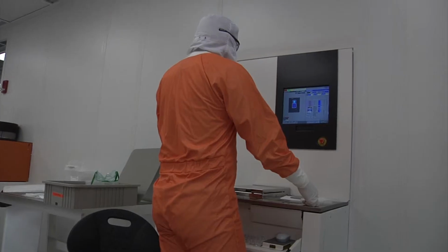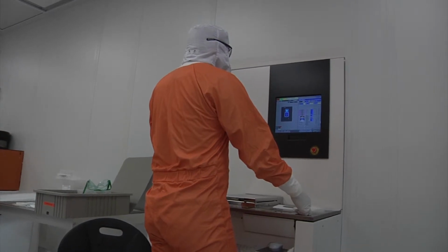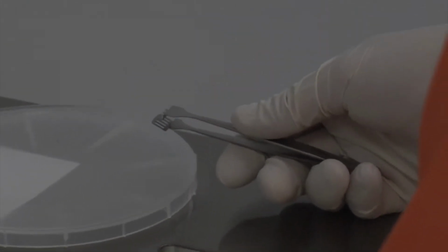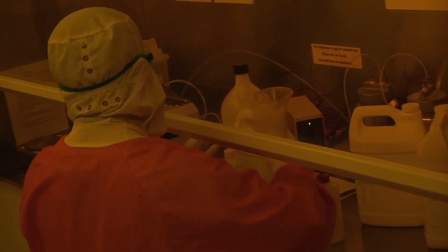The other reason is we put the mass of the equipment back in the chases. Again, that helps from a cost standpoint, but the big thing there is the people who are working on the equipment are the only ones allowed in the chases. So what we're doing by using a bay chase design with the mass of the equipment, the repair side, in the chase, protects the equipment from people turning the wrong knob, something like that. Where in the clean room, the bay area of the clean room is the only place that research materials are exposed. So they're only exposed in the cleanest area of the clean room.